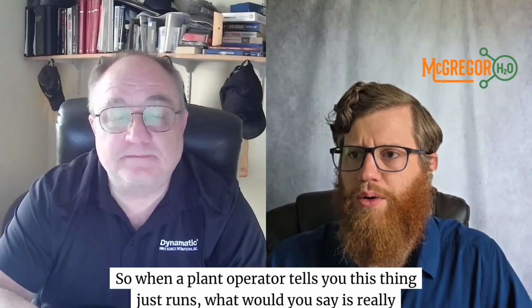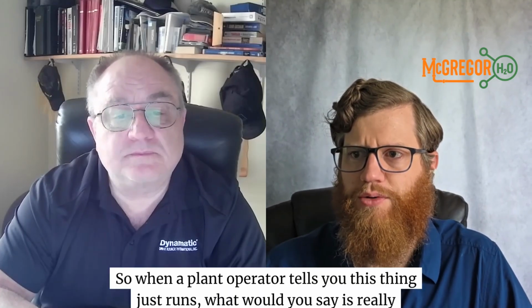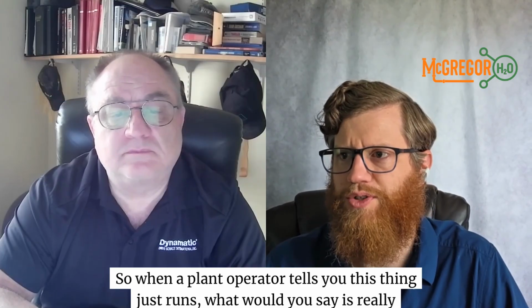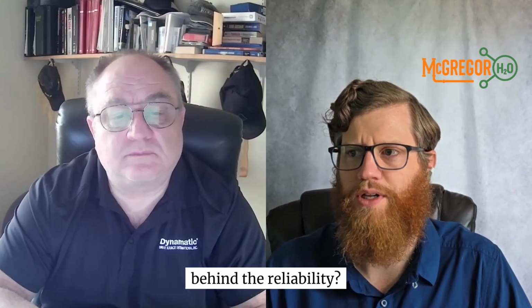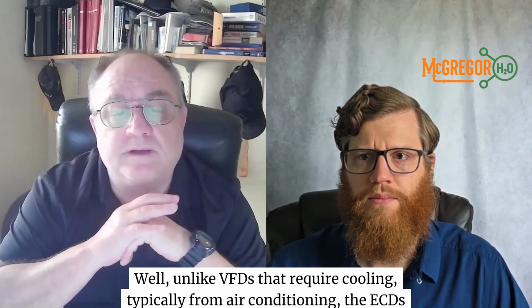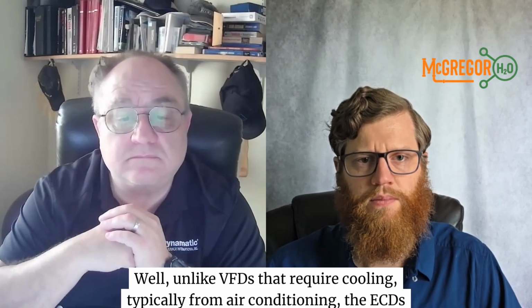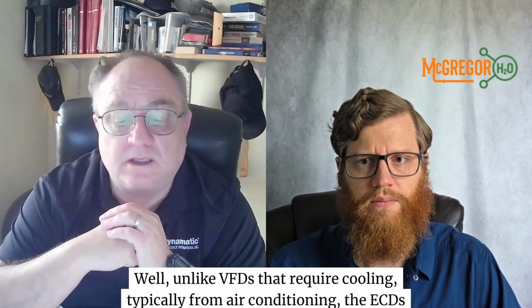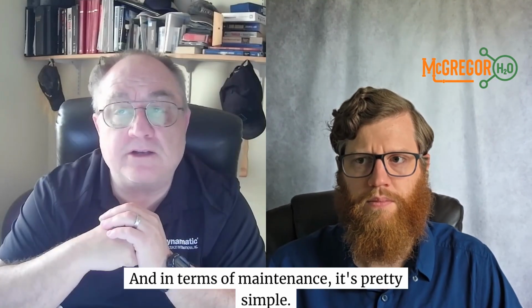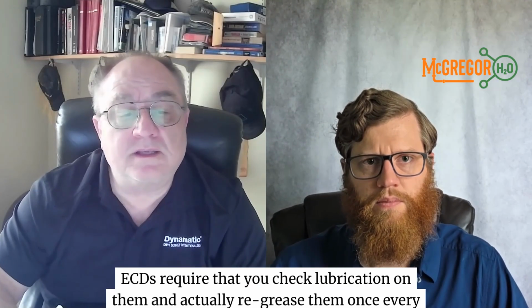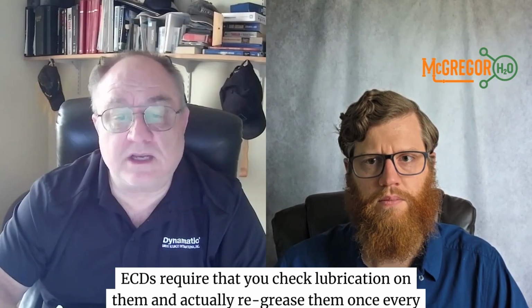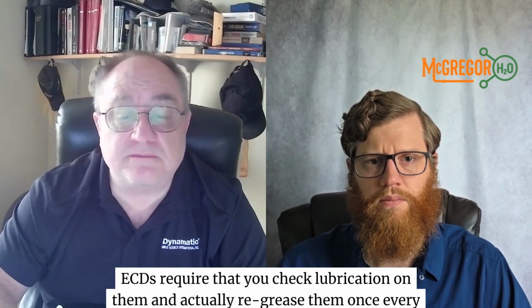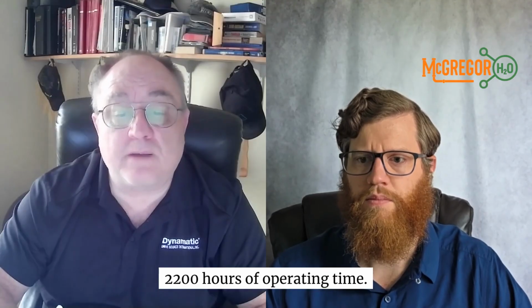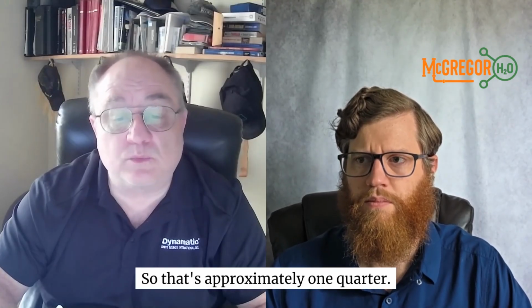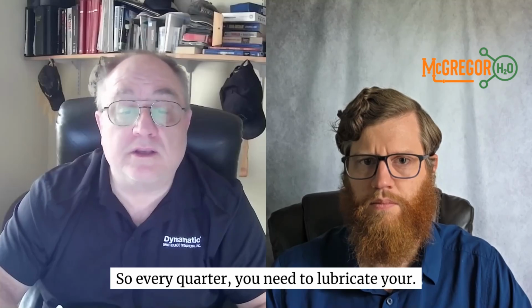You bet. So when a plant operator tells you this thing just runs, what would you say is really behind the reliability? Well, unlike VFDs that require cooling, typically from air conditioning, the ECDs don't require that. And in terms of maintenance, it's pretty simple. ECDs require that you check lubrication on them and re-grease them once every 2,200 hours of operating time. So that's approximately every quarter, you need to lubricate your eddy current drives.